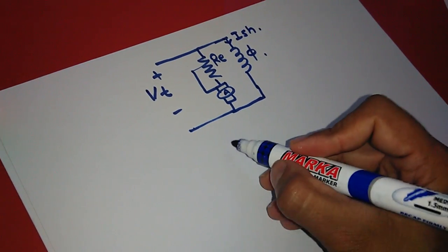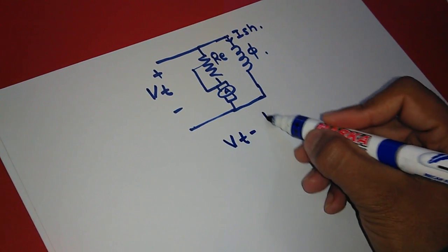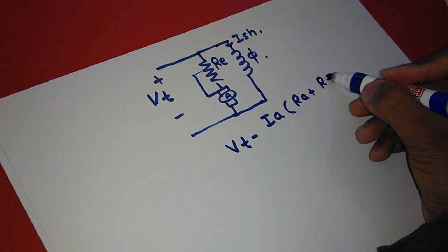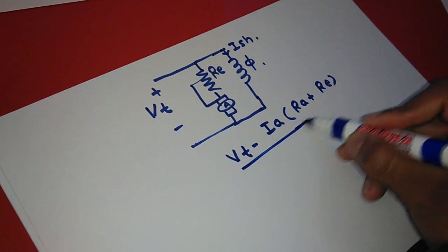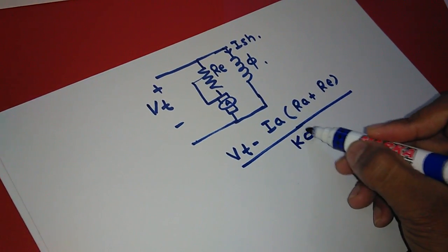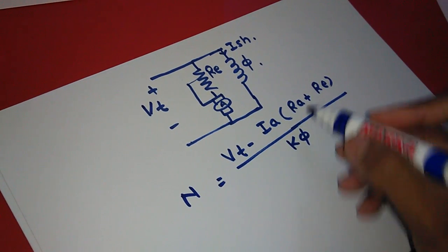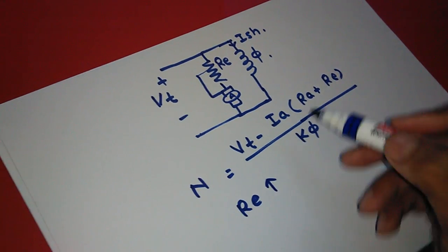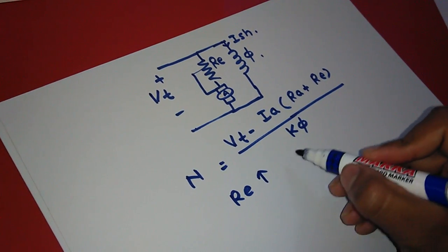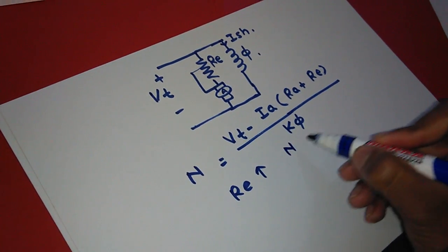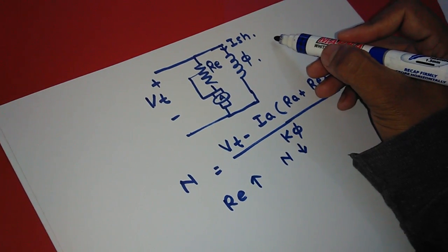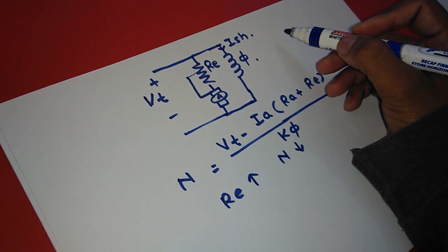From this method we can see that N is proportional to Vt minus Ia(Ra plus Re) upon Kφ. By changing the external armature resistance, the Ia Ra drop will be increased so that speed is also decreased. In the case of series motor or shunt motor this method can be done easily, and for small motors this method is suitable.